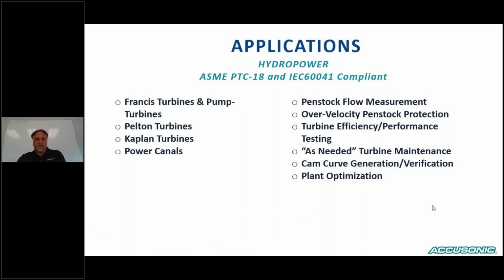The other thing that the flow measurement can be used for is to create an as-needed turbine maintenance program, as opposed to just doing something annually every year. For those Kaplan units that maybe were just upgraded or overhauled, you can redo your cam curves, verify that your current cam curves are the optimum setting for the wicket gate and blade angles.